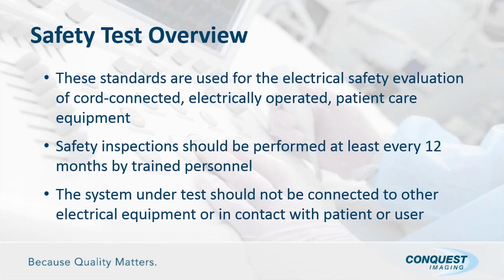ACR requires that these electrical safety inspections be conducted every 6 months at a minimum, and goes on to say that if you repair a piece of equipment, a power supply or circuit board, that you should, after that repair, conduct the electrical safety again. So the system under test should not be connected to other electrical equipment or in contact with a patient or user. That's a pretty big thing, because some of the things we do during electrical safety actually create an unsafe condition, or potentially unsafe condition, on the equipment. And we don't want to introduce that to the patient or, in fact, the operator or ourselves.